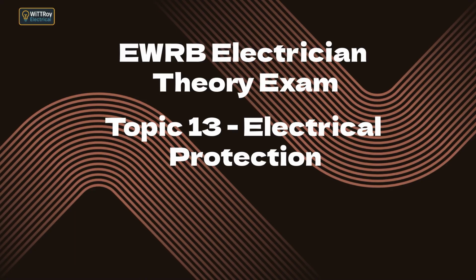13.3c Explain why it is necessary, when two or more electrical appliances are connected simultaneously to one isolating transformer, that their earth continuity conductors are bonded together at the transformer but must not be earthed. If more than one appliance is connected to an isolating transformer, all exposed metal parts must be kept at the same electrical potential. To achieve this, the earth continuity conductors must be bonded together at the transformer. This ensures all appliance frames sit at the same voltage.